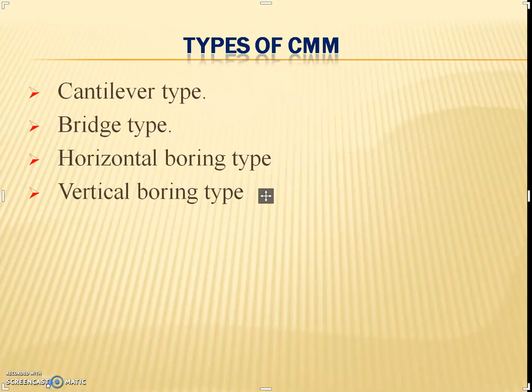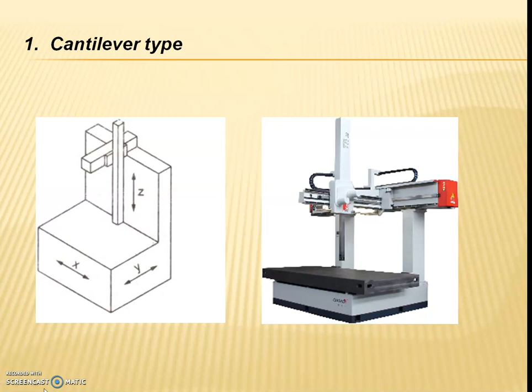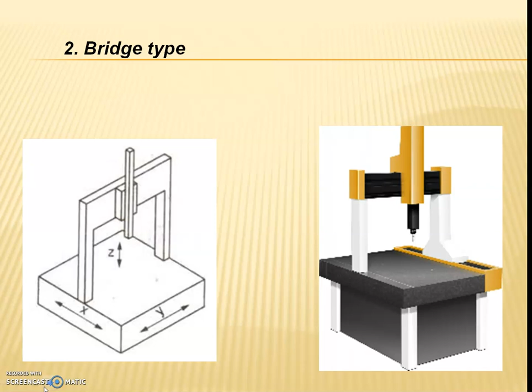Types of CMM: cantilever type, bridge type, horizontal boring type, vertical boring type. The cantilever type is easy to load and unload, but it is most sensitive to mechanical error because of sag or deflection in the Y-axis beam. Bridge type: it is difficult to load but less sensitive to mechanical error. A floating bridge type machine is also available, in which the complete bridge can slide in the Y direction.